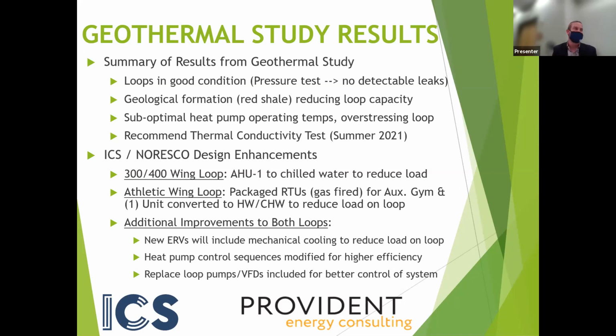So one is you reduce the load that's on those well fields. We do that by converting air handling units and systems over to chilled water and hot water. Again, you guys have this brand new chiller plant. Part of this package is a boiler plant. So we want to maximize those systems and move as much as we can to the chilled water and the hot water systems.